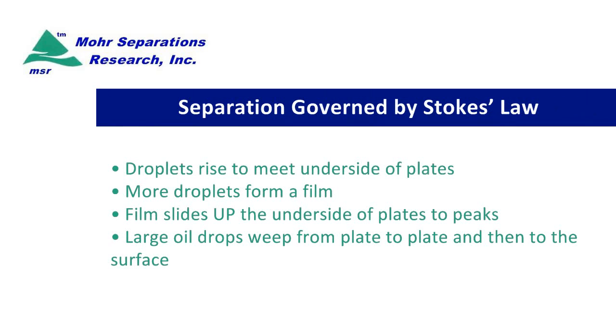The droplets rise to meet the underside of the plates. As more droplets come along they form a film. The film slides up the underside of the plates by their buoyancy and comes to the peaks of the plates. Large oil droplets then weep from plate to plate to plate and then to the surface. With this kind of system we're actually converting droplets less than 40 microns — smaller than what the human eye can see — into really large drops the size of a grape or perhaps the end of your thumb.